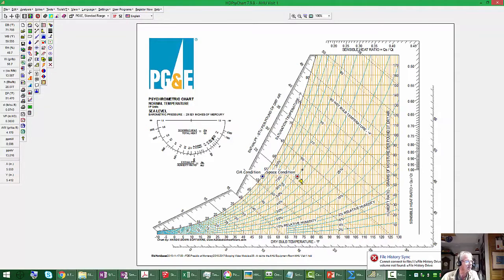Now the space condition may or may not be the return condition. Most of the time there's heat gains in the return, if for no other reason than the light fixtures are sticking up into the return plenum a lot of times, and so some of the heat from the light ends up in the return air. If there's a roof load, that'll end up in the return air.